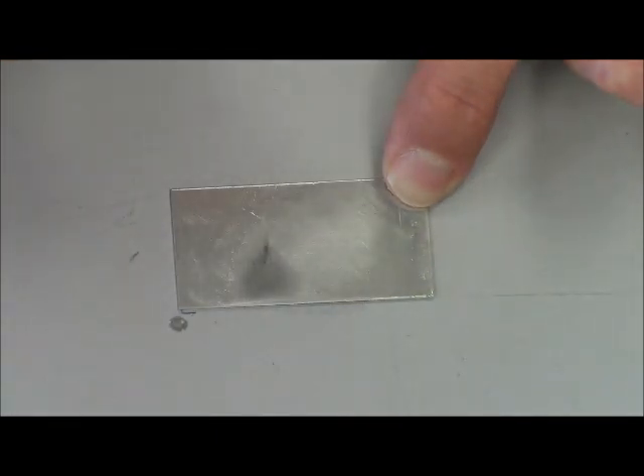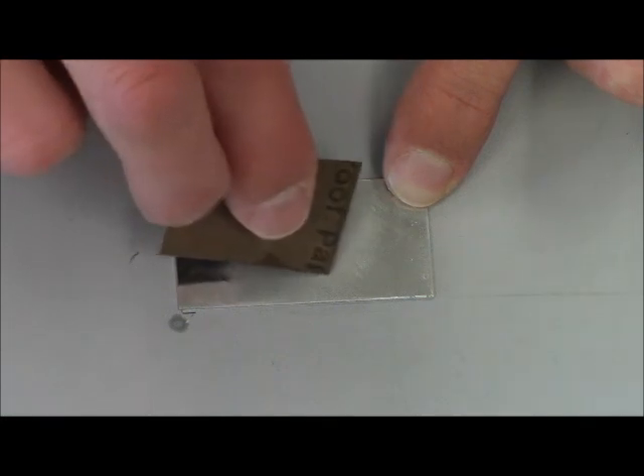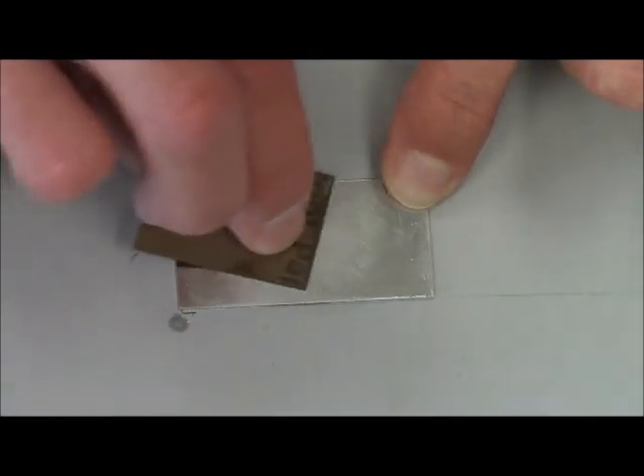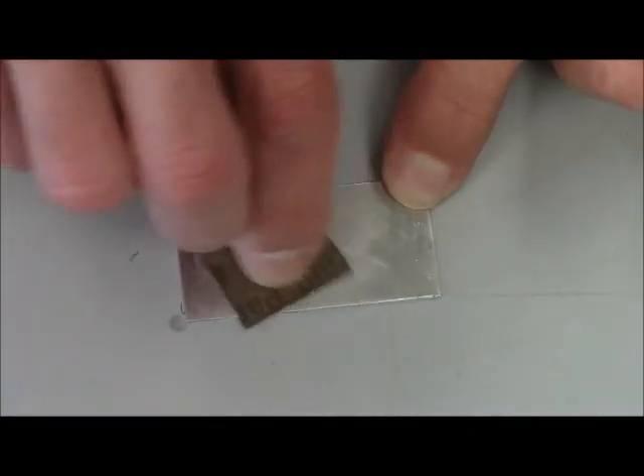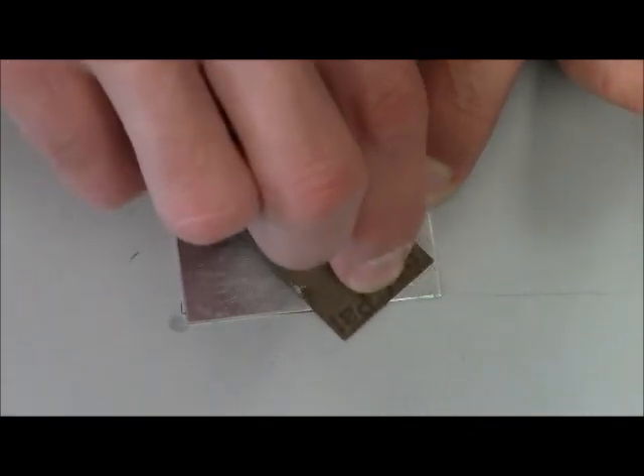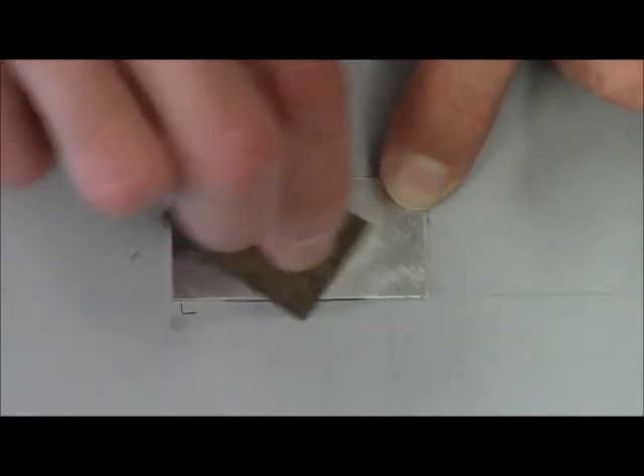I'm going to do about 10 to 15 strokes back and forth. Now, I want to make sure that I get an area that's big enough for the application of the strain gauge. I don't need to necessarily sand the entire piece. Now, I've done more than 10 to 15 strokes, but I'm just trying to make sure I get an area big enough. 10 to 15 is a recommendation. If you go more, that's fine.